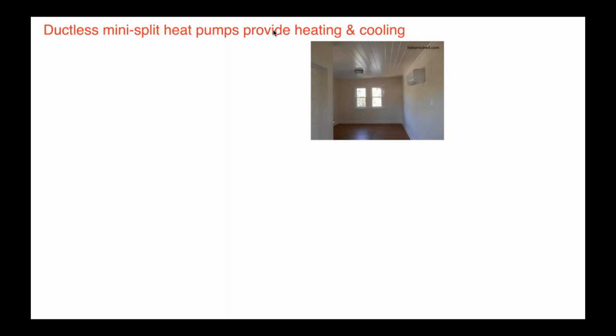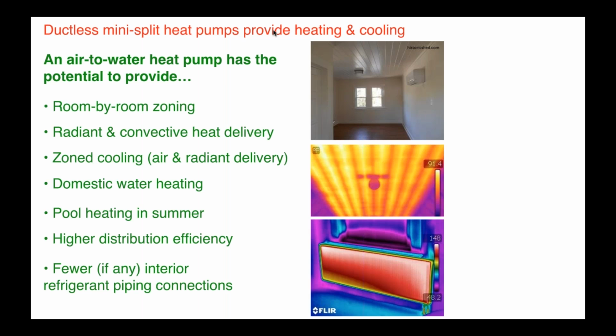So again, ductless mini splits, they provide heating and cooling. If you go to air to water, look at all the things you can do here. Room by room zoning is easy. Radiant convective heat delivery, if you're doing radiant panels, floors, walls, ceilings, panel radiators. You could do zoned cooling if you want to. You can do domestic water. Some heat pumps can have a secondary heat exchanger that in the summer, if you happen to have a pool, instead of dumping heat outside to cool the house, you could dump it into a swimming pool, okay?